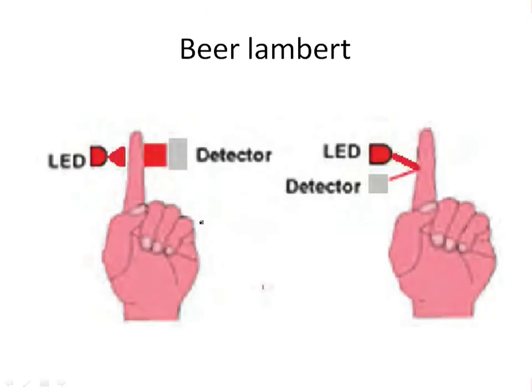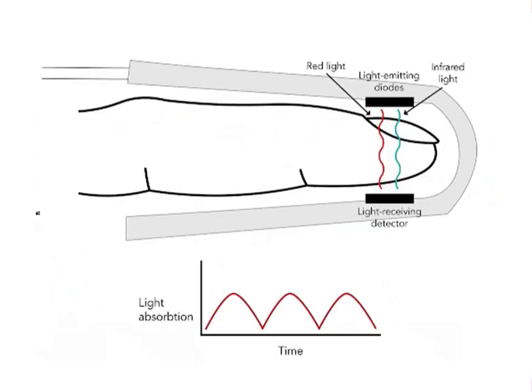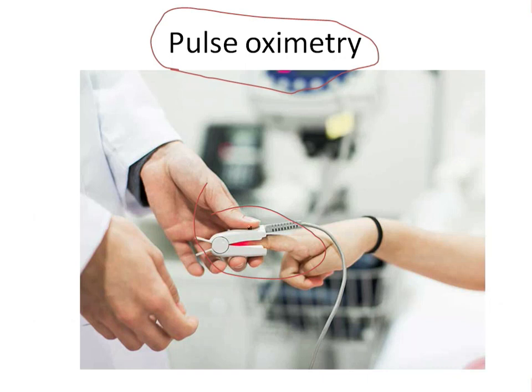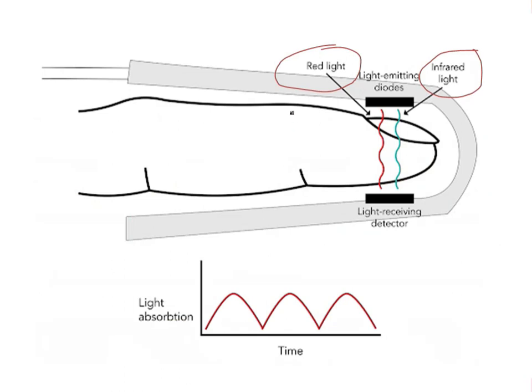Now, the concept of the pulse oximeter is we have what is called the light emitting diode. It works by two wavelengths: one of them is red wavelength, about 660 nanometers, and the other one is infrared light, with wavelength about 940 nanometers.